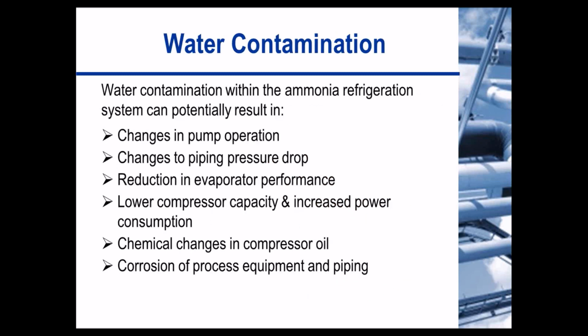So let's take a minute to talk about water. Water contamination within the ammonia refrigeration system is a bad thing and actually causes many operational issues as well as safety issues. What we see when we get water in our systems are changes in pump operation, changes in piping and pressure drop, reduction in evaporator performance, lower compressor capacity and increased power consumption, and chemical changes in compressor oil and corrosion of process equipment and piping. Many of these should clue you into the fact that you have water in your system. So as you're doing your process management, you should be looking for these types of signs.